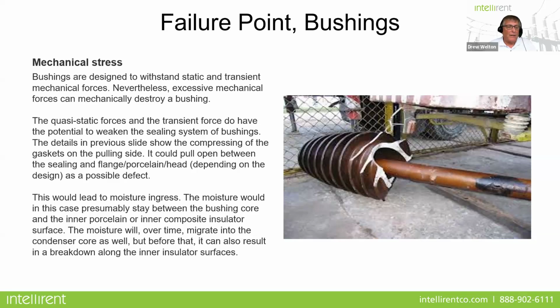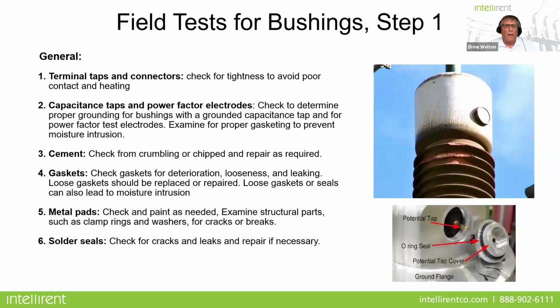And the moisture would, in this case, presumably stay between the bushing core and the inner porcelain or inner composite insulator surface. And the moisture will, over time, migrate into the condenser core as well. But before that, it can also result in a breakdown along the inner insulating surfaces. So let's talk first of all about some general field tests, and we'll get into this a little bit later towards the end of the presentation.